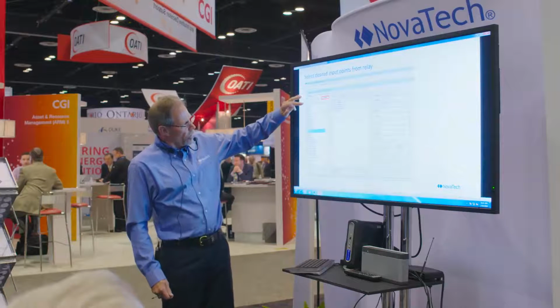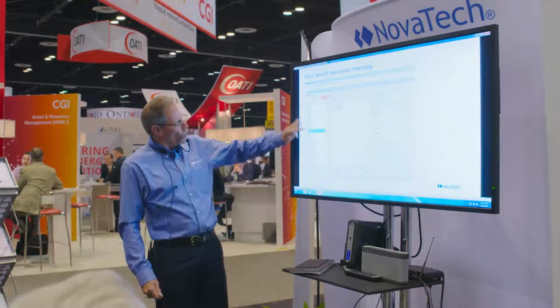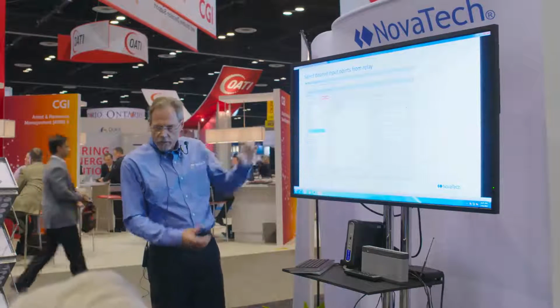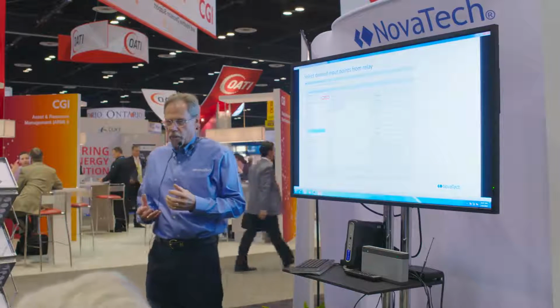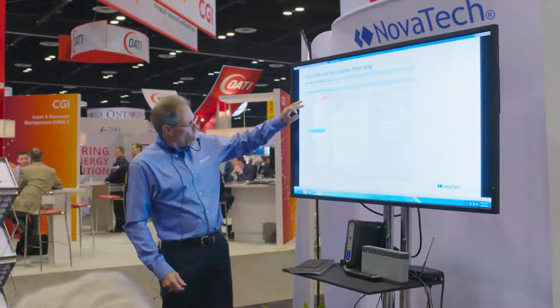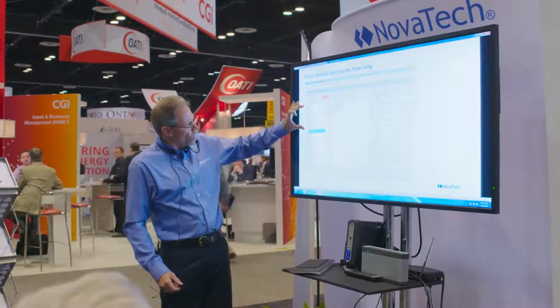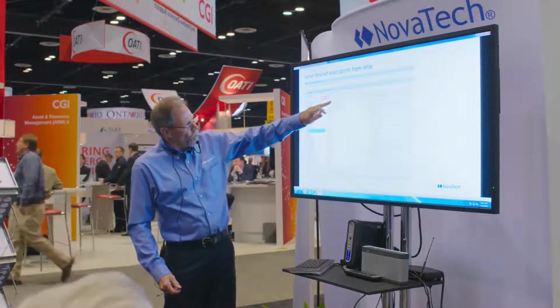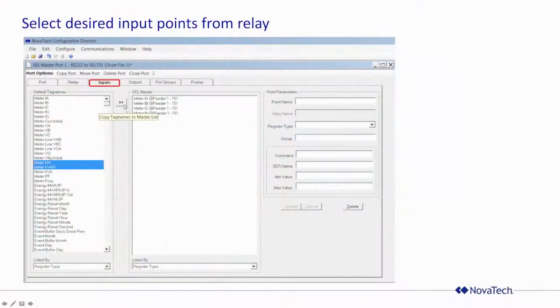The next thing is I'm going to go through the default tag names — this is all that pick list, all those points we've created for you. Now all you have to do is select the quantities you want, map them over, and that becomes the SEL master port — those are the points the Orion will pull back from that relay on that port.